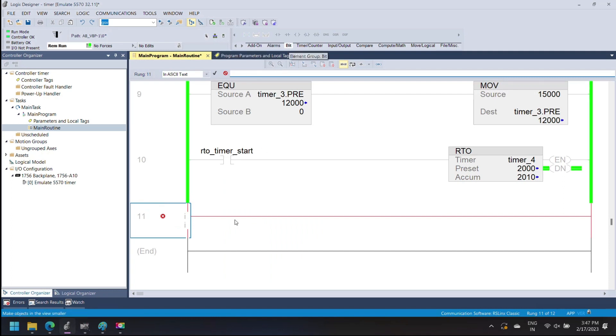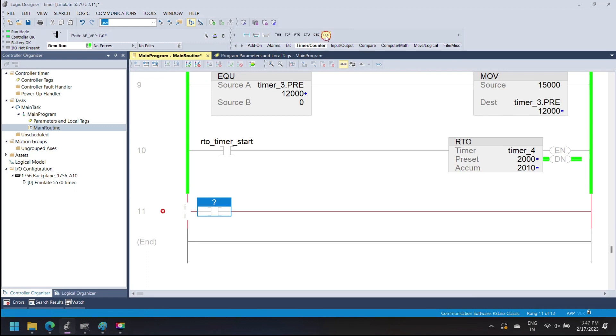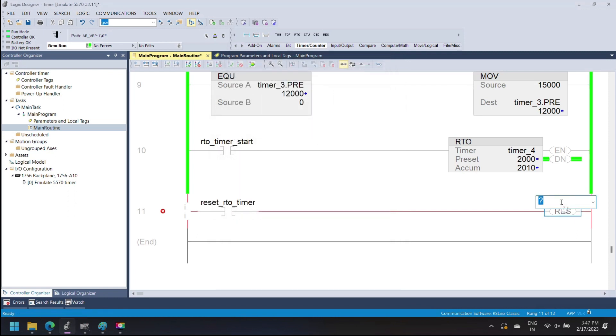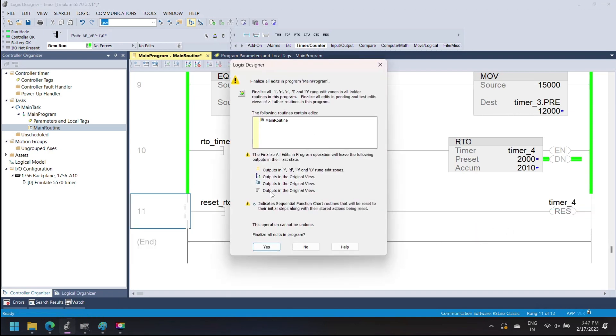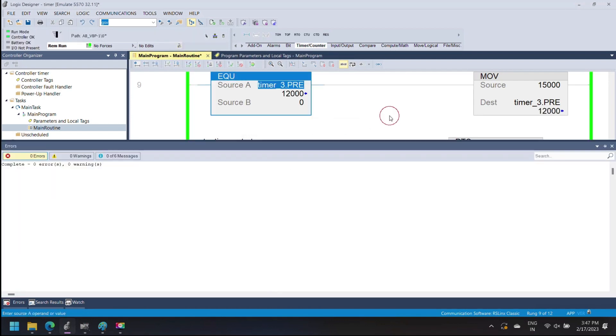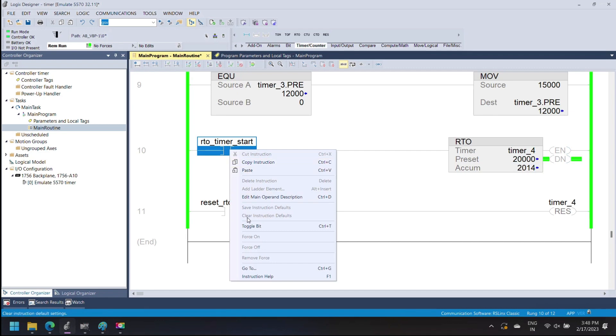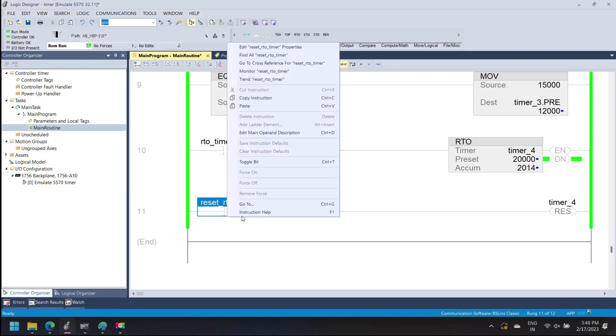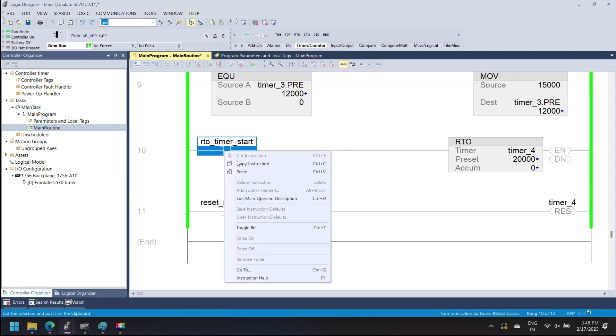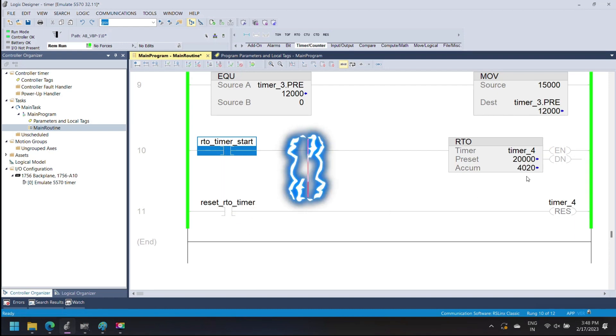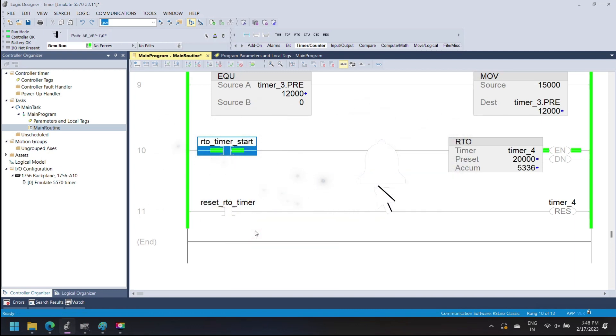As you can see, when the timer done bit is set to true in a retentive timer, the timer operation does not restart. So we use the reset instruction to reset the retentive timer in RSLogix 5000 — simply add the reset instruction and define the timer name you want to reset. As you can see, when the timer input bit changes from false to true the retentive timer starts, but when the input bit changes from true to false, the accumulator stores the recent time value. When the input bit changes again, the timer starts from the stored accumulator value until it reaches the preset value.